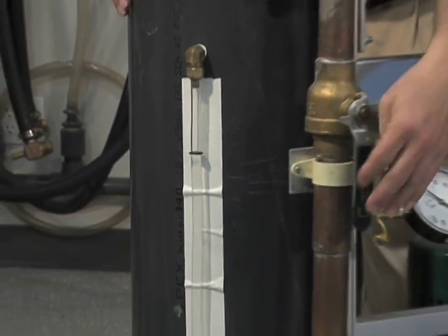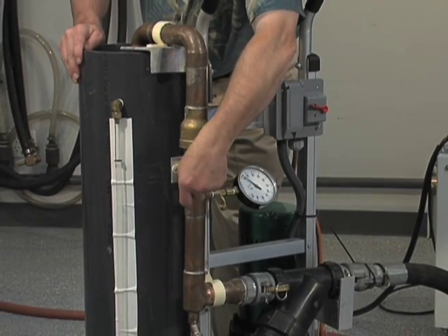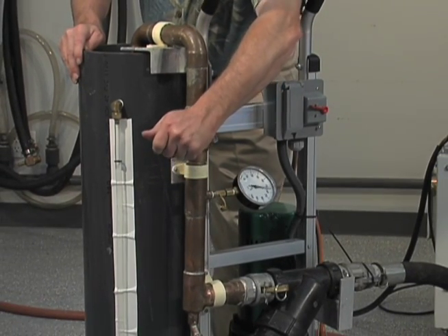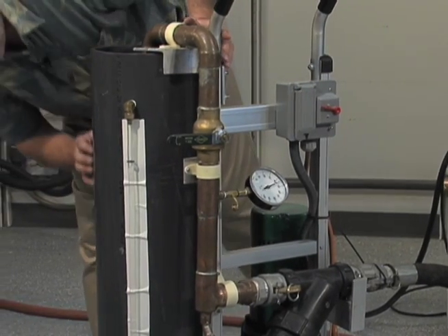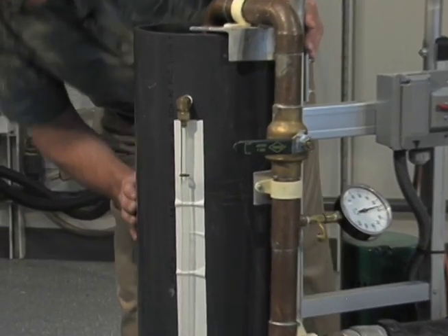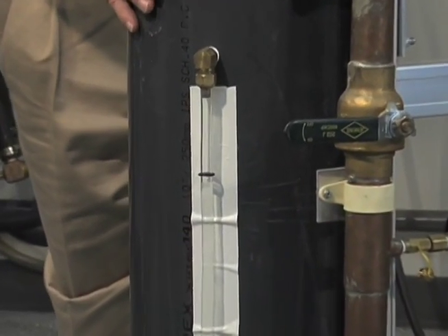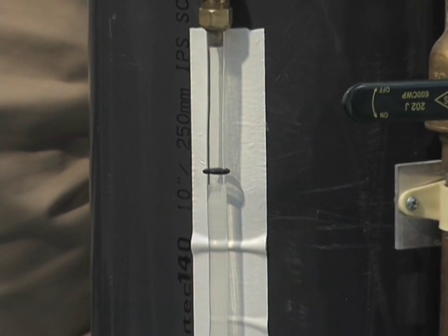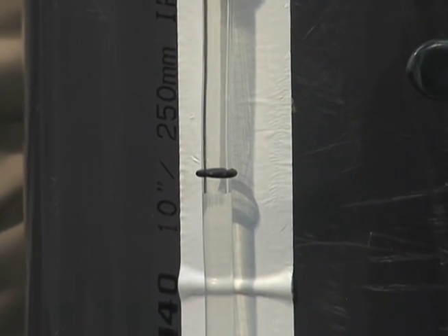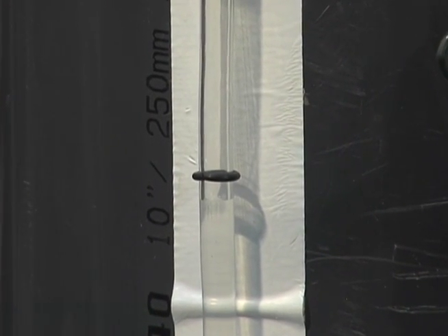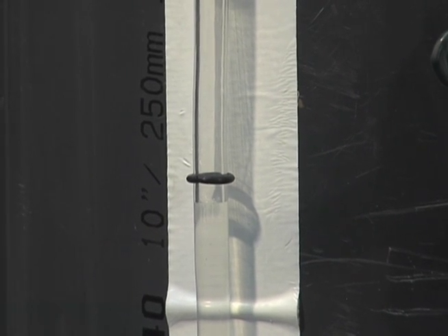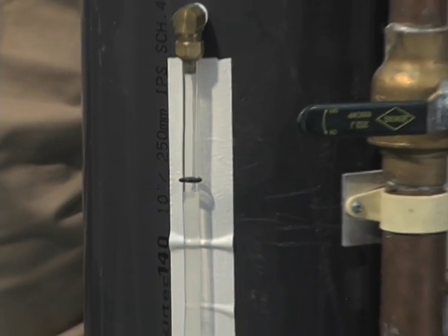And we're going to go ahead and deadhead this. Look for any drop in fluid level in our sight glass. As you can see here, we've got probably just slightly more than a 1/4 inch, 3/16, something of that nature. So I'm very confident at this point we have in fact removed all the air. So now we can do an integrity test of the system.